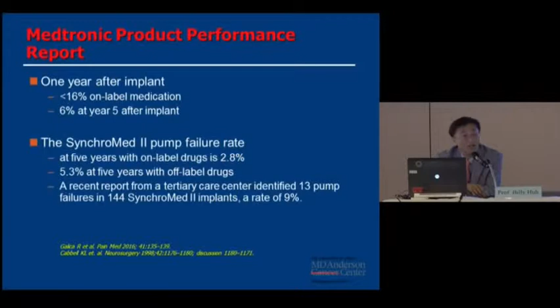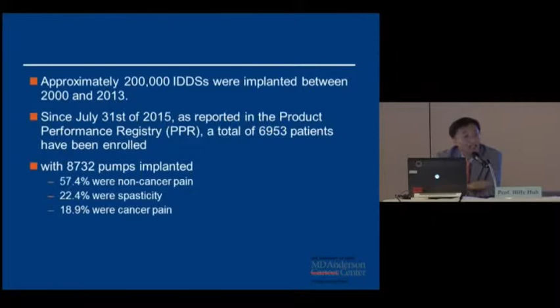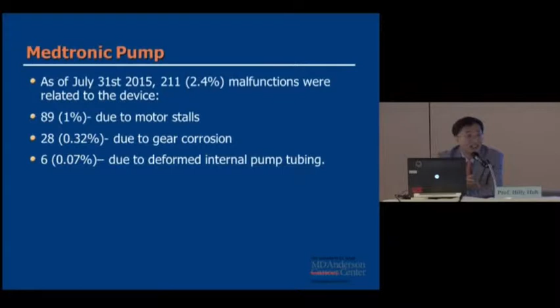Between 2000 and 2013, almost 200,000 pumps were implanted in the United States, and of those, about 7,000 have been registered. When they look at those pumps, almost 60% were for non-cancer patients, 22% for spasticity, and about 19% for cancer patients. So the vast majority of pumps are implanted for non-cancer patients. As of July 2015, there was a malfunction rate of about 2.4%: 1% due to motor stall, about 0.3% due to gear corrosion, and less than 1% due to internal pump tubing problems. Gear corrosion occurs because some of the non-FDA-approved drugs cause corrosion inside. When you withdraw the residual drug, it actually looks yellow because it causes rust inside the pump.